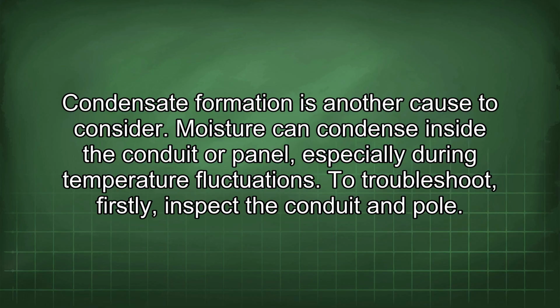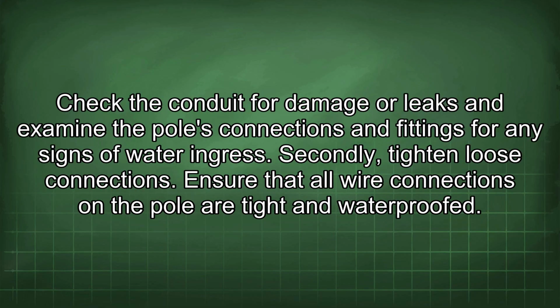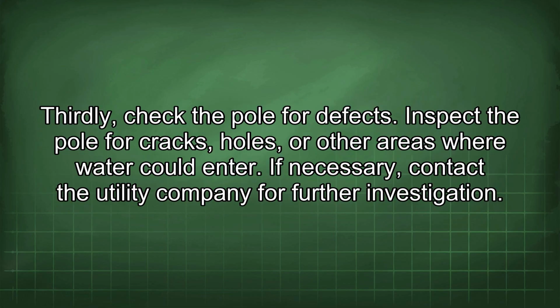To troubleshoot, firstly, inspect the conduit and pole. Check the conduit for damage or leaks and examine the pole's connections and fittings for any signs of water ingress. Secondly, tighten loose connections. Ensure that all wire connections on the pole are tight and waterproofed. Thirdly, check the pole for defects. Inspect the pole for cracks, holes, or other areas where water could enter. If necessary, contact the utility company for further investigation.